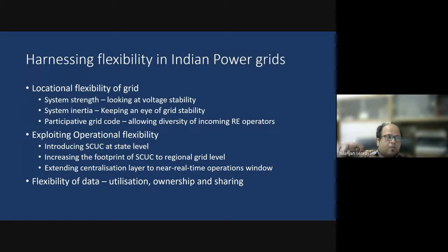So therefore, we need to have a node-wise mapping of the system strength so that we can come up with the hosting capacity at these locations. At every node, we need to come out with a hosting capacity. How much power can be injected into that node? And this must be periodically updated, typically maybe annually, and if not annually, every time the grid undergoes a significant change, this hosting capacity must be remapped.